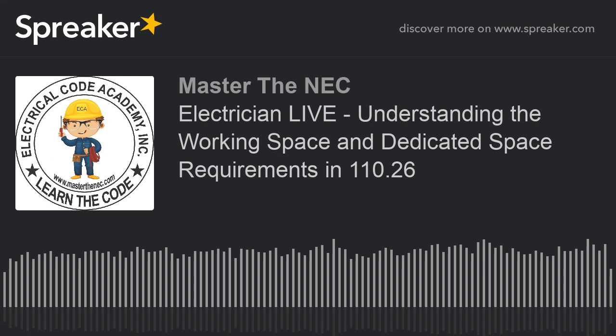And B has to do with low voltage. Now, again, controversial use of the term low voltage because, again, anything that is 2,000 volts or less is really considered low voltage. But in this context, they're going to give you voltages so you can kind of understand where they're coming from. It's low voltage. So it says by special permission. Now, interesting. When it says by special permission, that means that you need to get special permission from the AHJ. And again, special permission should be in writing, allowing you to deviate from the general rule. It says by special permission, smaller working spaces shall be permitted where all exposed live parts operate at not greater than 30 volts RMS, 42 volts peak, or 60 volts DC.